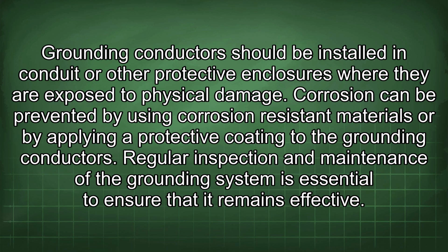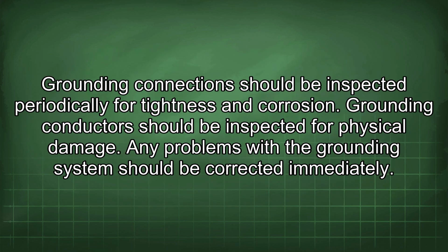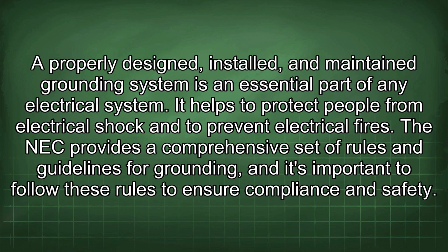Regular inspection and maintenance of the grounding system is essential to ensure that it remains effective. Grounding connections should be inspected periodically for tightness and corrosion. Grounding conductors should be inspected for physical damage. Any problems with the grounding system should be corrected immediately. A properly designed, installed, and maintained grounding system is an essential part of any electrical system. It helps to protect people from electrical shock and to prevent electrical fires. The NEC provides a comprehensive set of rules and guidelines for grounding, and it's important to follow these rules to ensure compliance and safety.